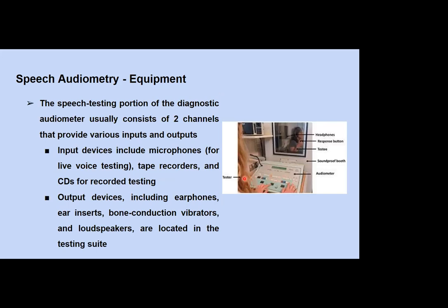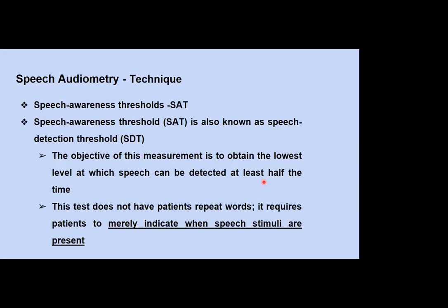A typical speech audiometer is placed in the control room. It has a microphone and other input devices such as a CD player or tape recorder through which speech stimuli can be presented. These are delivered through output devices placed inside the test room, which include earphones placed on the ears, insert earphones inserted into the ear canal, bone vibrators, or loudspeakers. The speech stimuli are presented through these output devices or transducers to the person being tested.